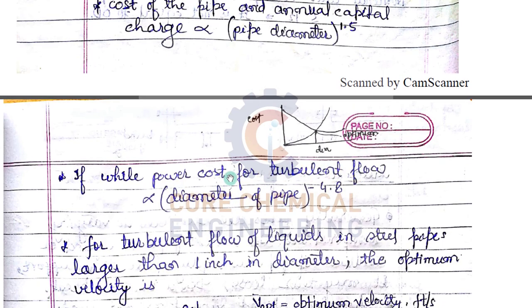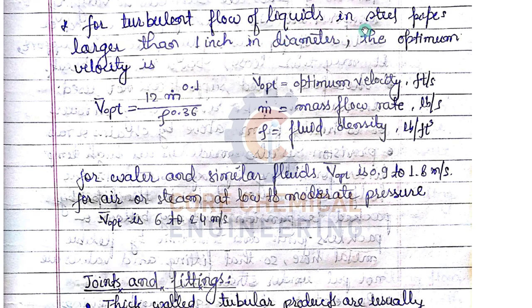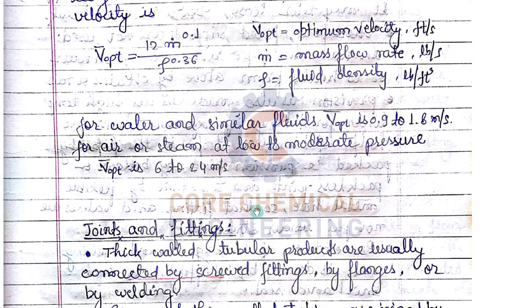For turbulent flow of liquid in steel pipes larger than one inch diameter, the optimum velocity is: v_optimum = 12 × ṁ^0.1 / ρ^0.36 (in feet per second, where ṁ is mass flow rate in lb/s and ρ is density in lb/ft³). For water and similar fluids, v_optimum is 0.9 to 1.8 m/s; for air or steam at low to moderate pressure, it is 6 to 24 m/s.